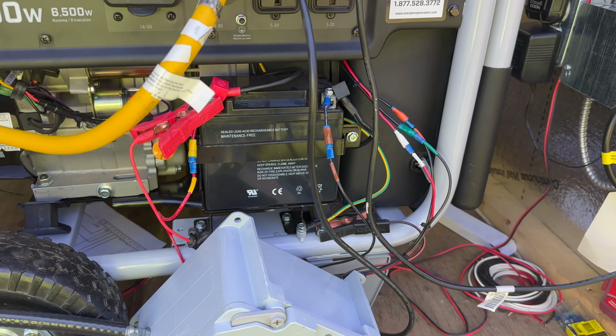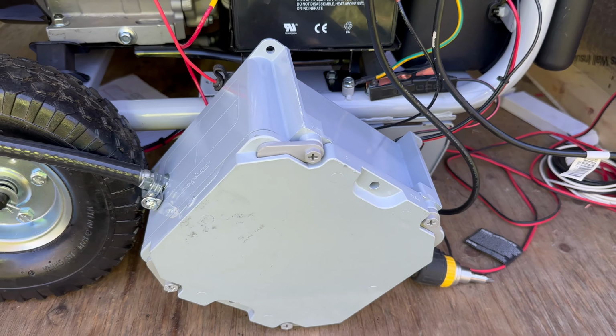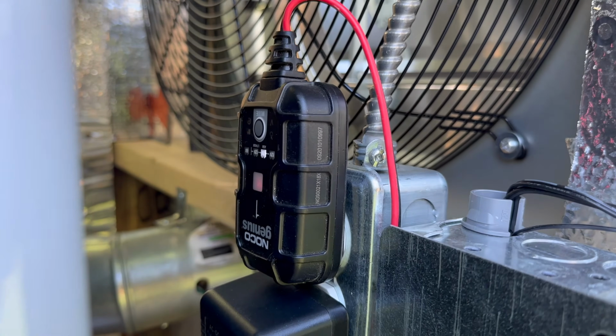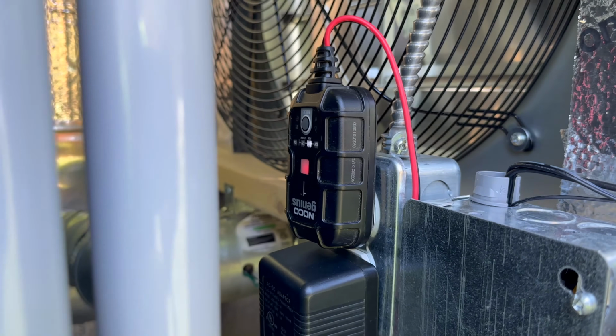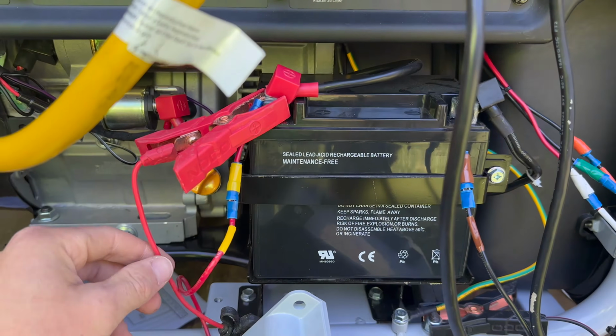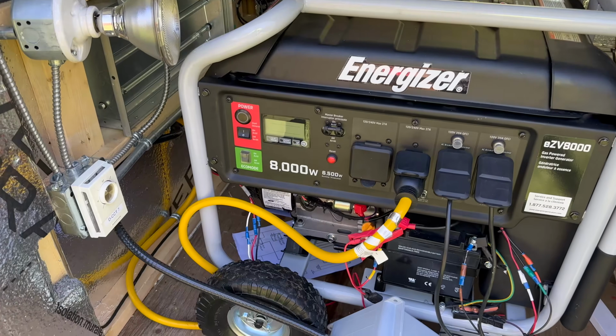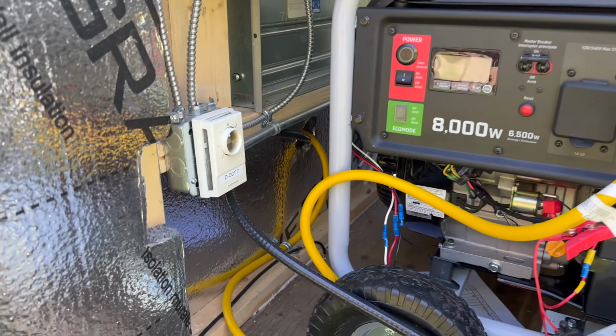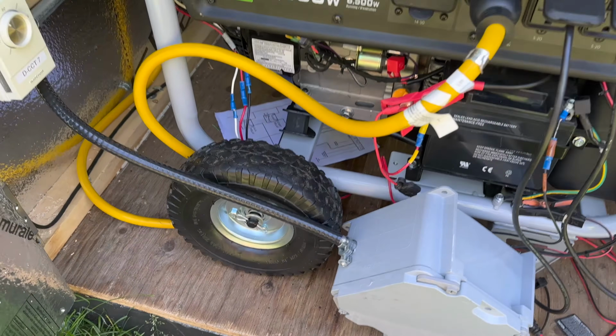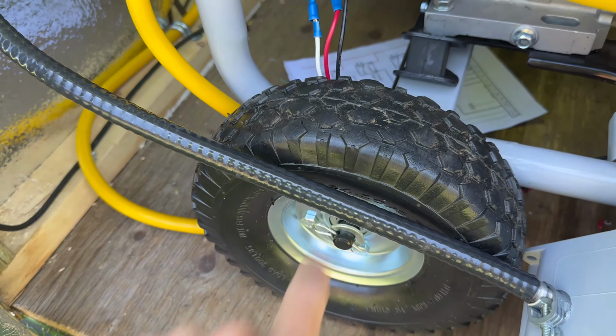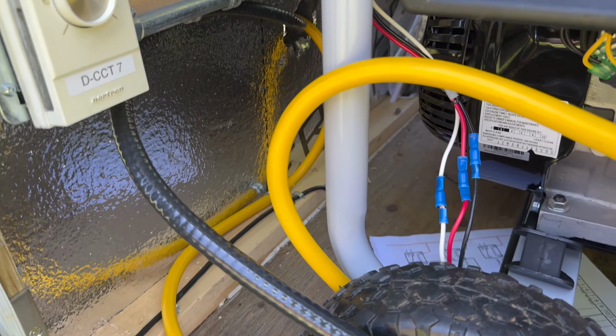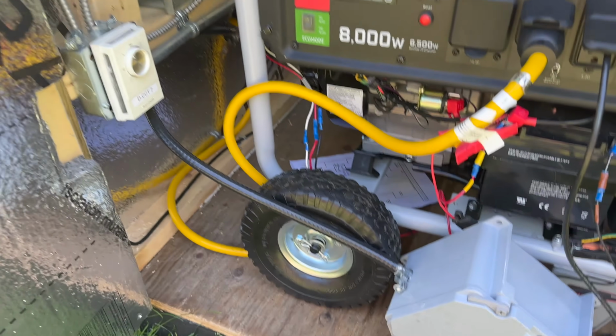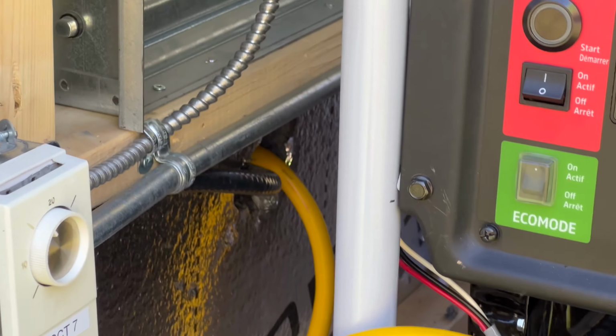The last component in here, as this does draw constant 12 volts off of the generator's battery, is I have this little 12 volt charger. It's just a 1 amp charger that keeps the battery charged. I have a clip on the positive and a clip on the ground or the negative of the battery, just to keep it charged up. The generator power goes through that yellow cord out the side of the generator building. Same with this black cable here, which is that power that goes to the module to tell the generator when to start. They both go into that hole right there.